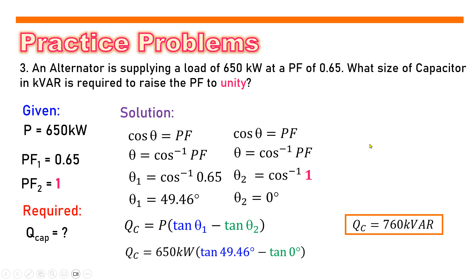Mapapansin natin na lahat ng capacitor bank natin ay nakalagay sa kVAR. Pwede nating i-convert yung ating size na nakuha from kVAR to farad dahil ang unit naman talaga ng capacitor ay farad, pwede siya sa kVAR, pwede rin siya sa farad. Para ma-convert yung kVAR to farad, we simply use the formula C, which is the capacitance in farad, equals Q sub C, or the reactive power ng ating capacitor in kVAR, divided by 2 pi F V squared.